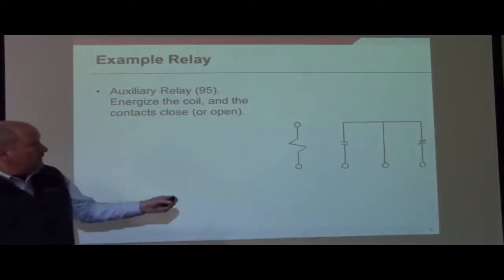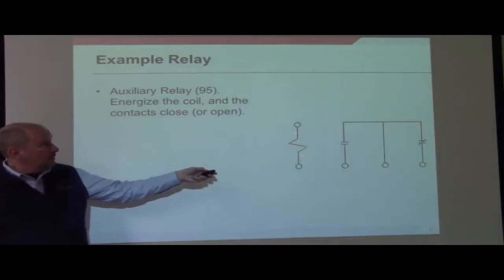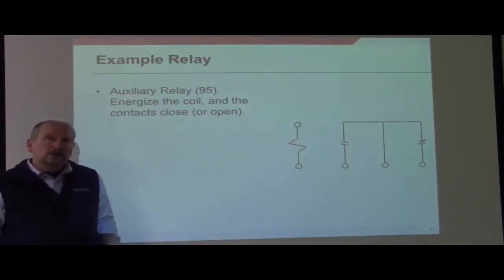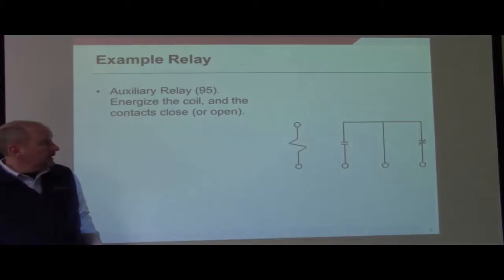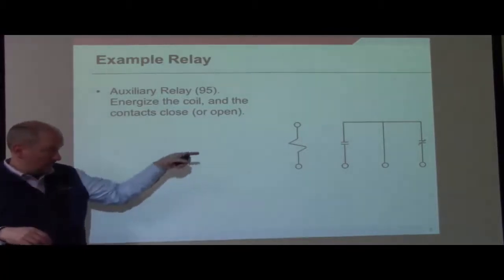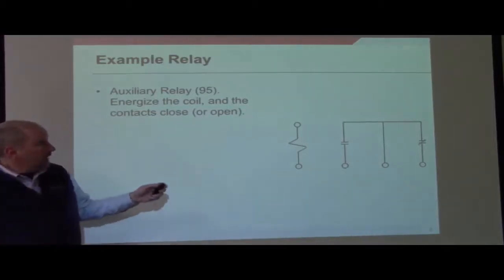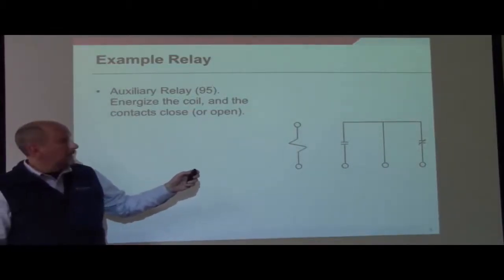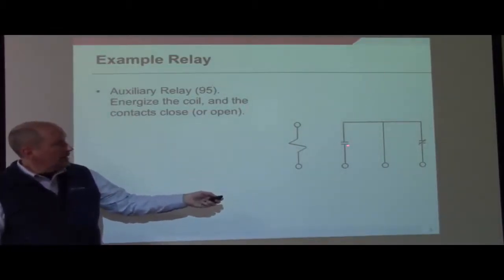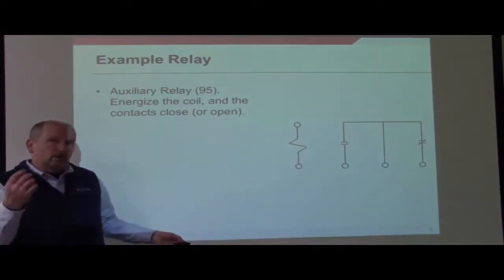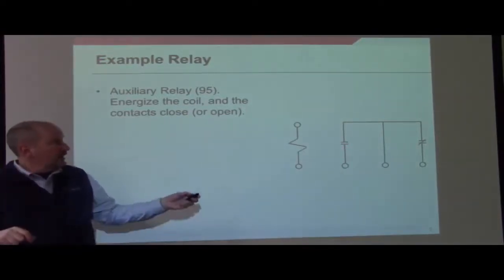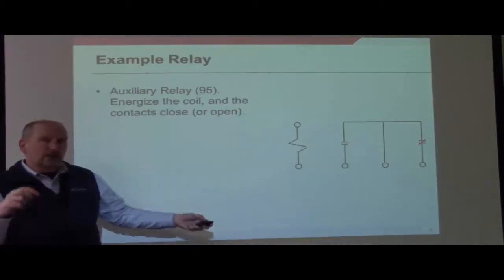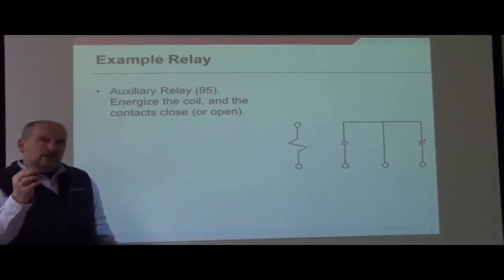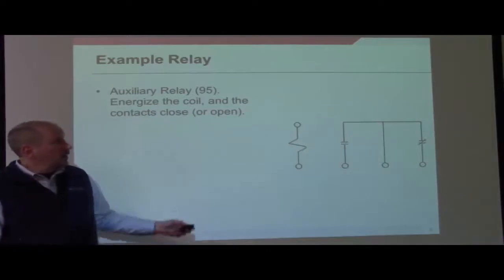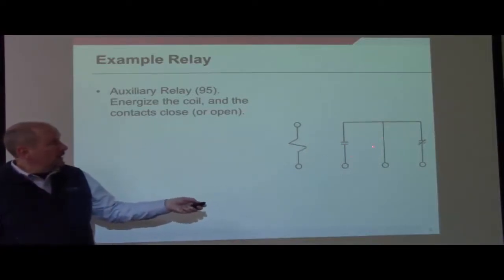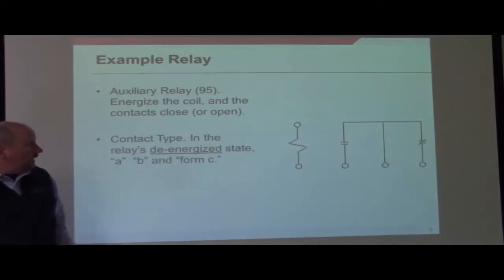The symbology for this will use this symbol, which is basically a coil, and it can also be shown just as a circle, but more commonly as that little squiggly line. Now the output of these relays is typically an A contact, which would be normally open, or open when it's de-energized. And you may also have B contacts that are closed when the coil is de-energized, but open when you energize that coil. Or you may have a combination of the two, and that we call a form C contact.